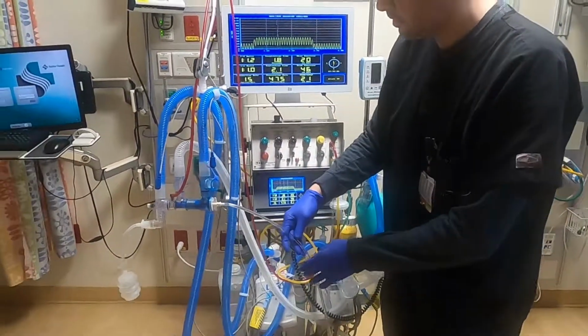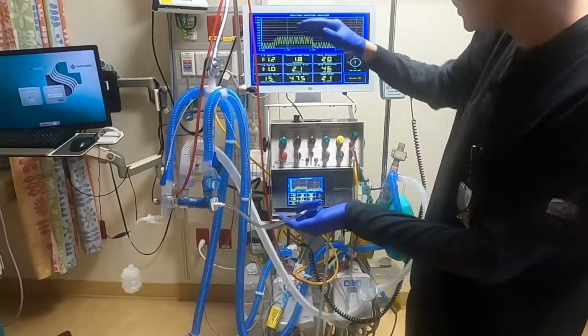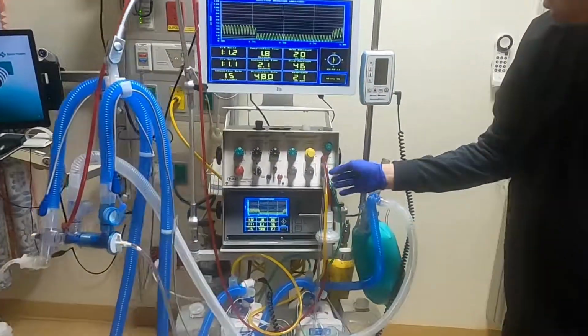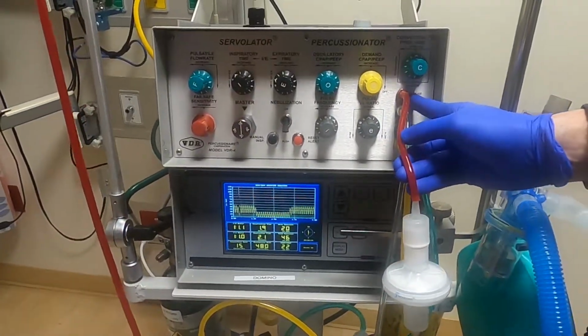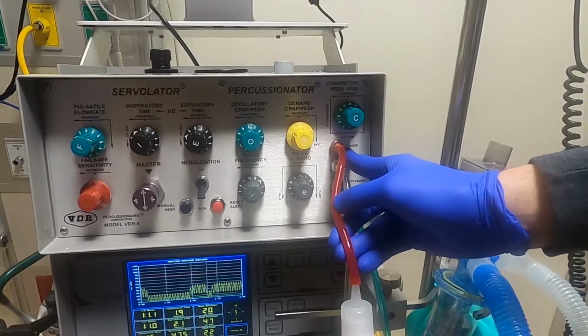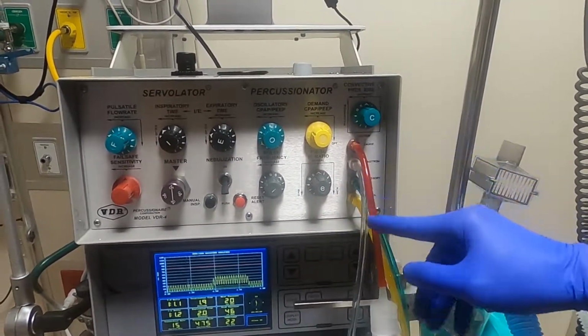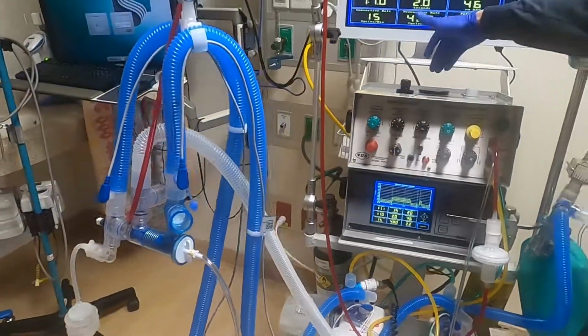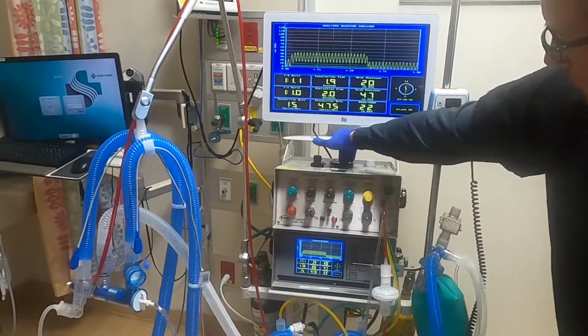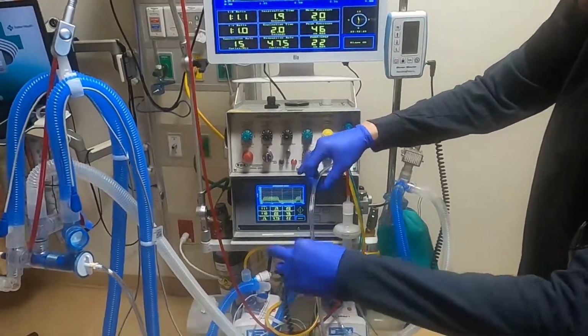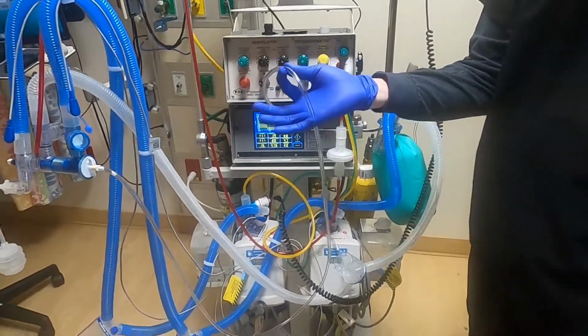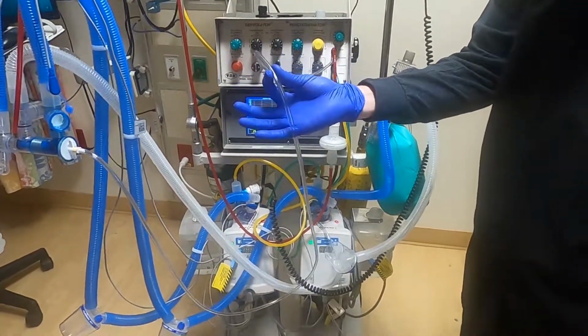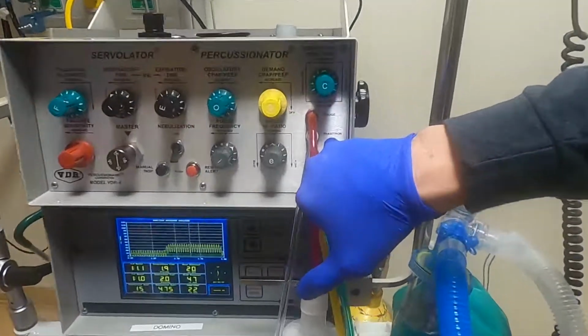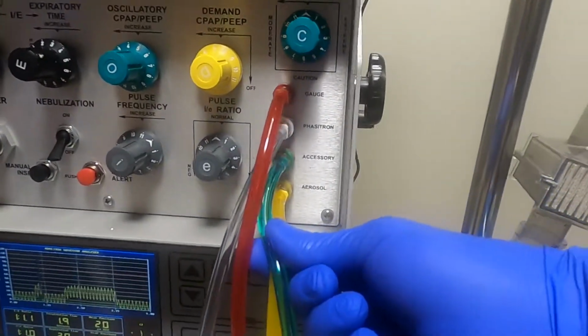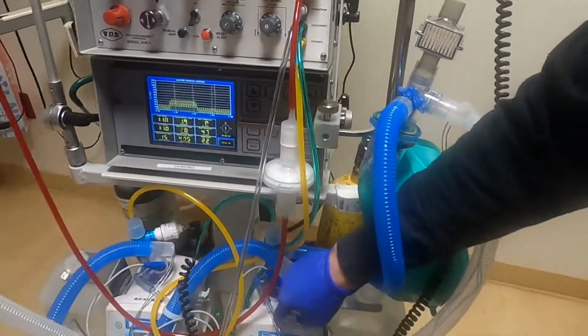Just a little bit about these tubes here. As you can see on the plate, we have your red monitoring line, which is basically your gauge, and this is what's sensing our settings and giving us our pressures on our gauge. And this is the Phasitron, which is the most important line. This is where all the ventilation is coming from. All the flow is coming through this tube here. You can see it says Phasitron there. These other two are just providing some extra flow to power our heaters and our humidification system that goes to the patient.